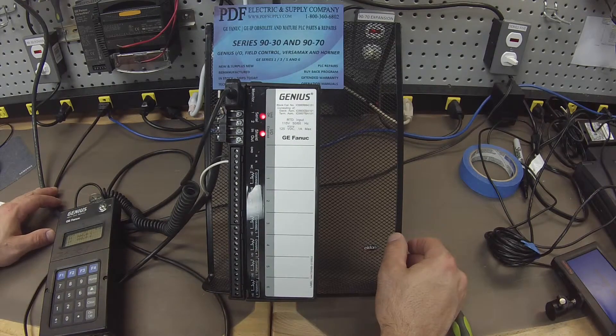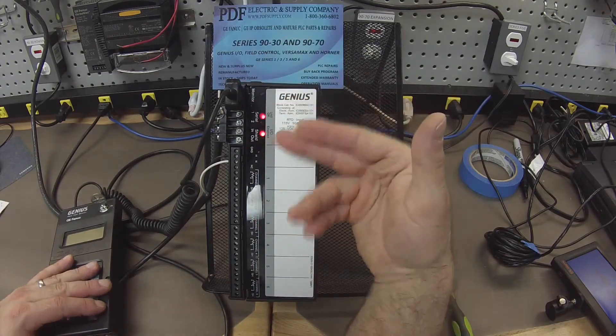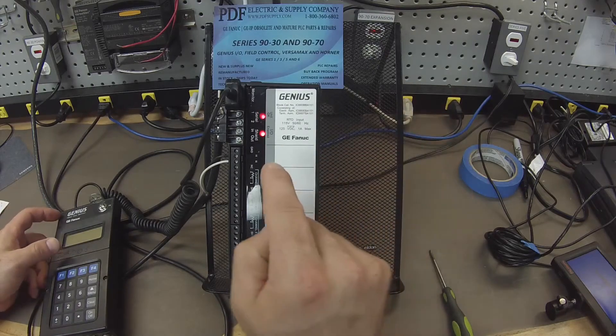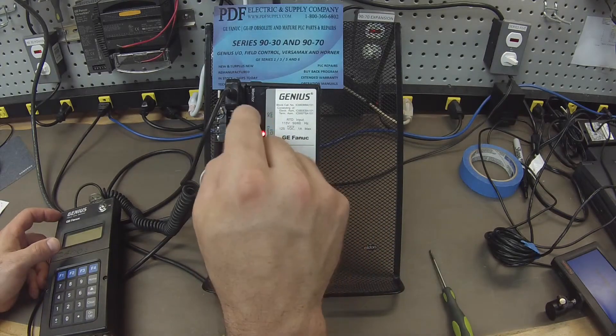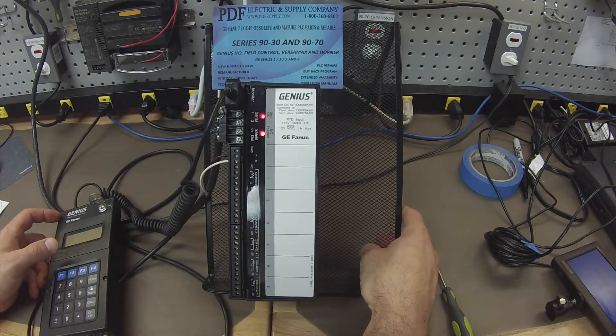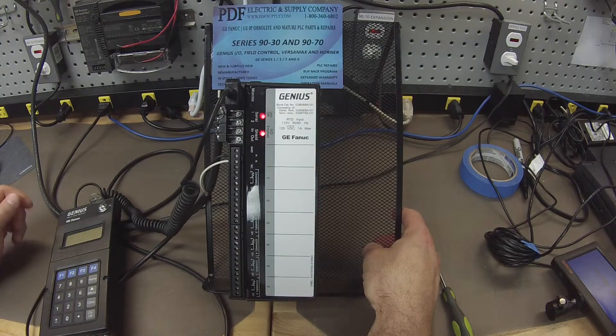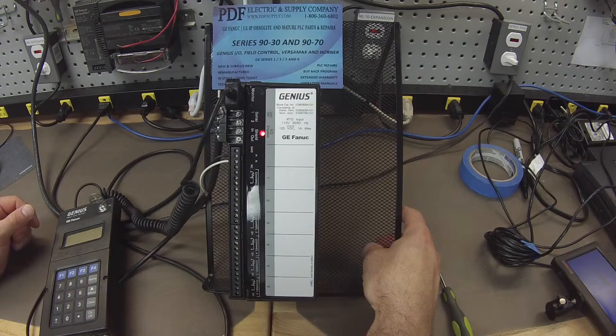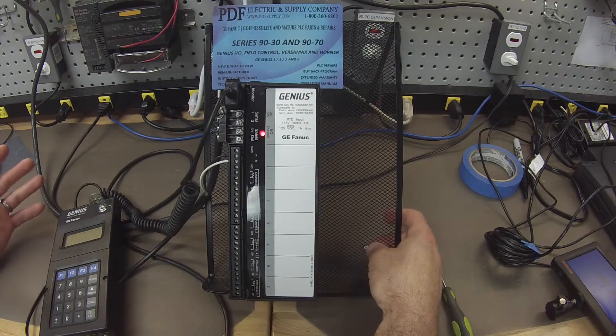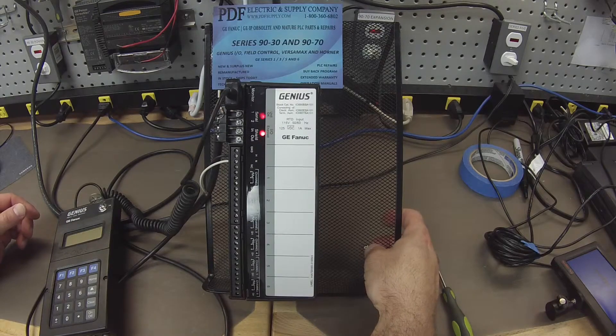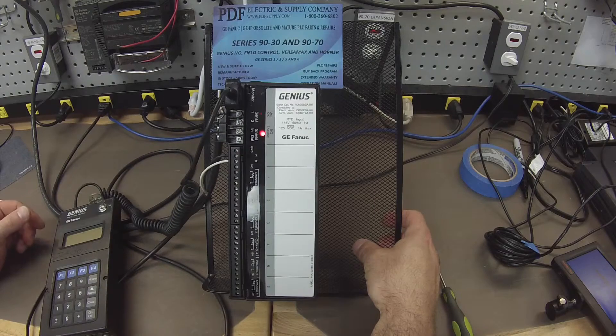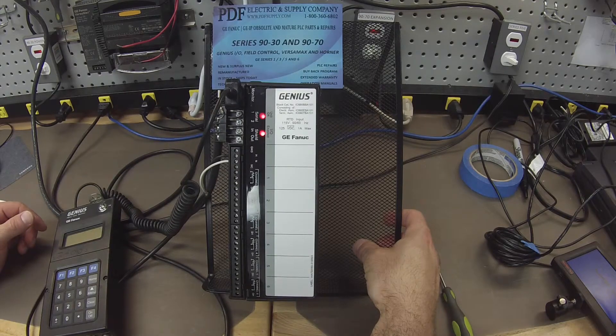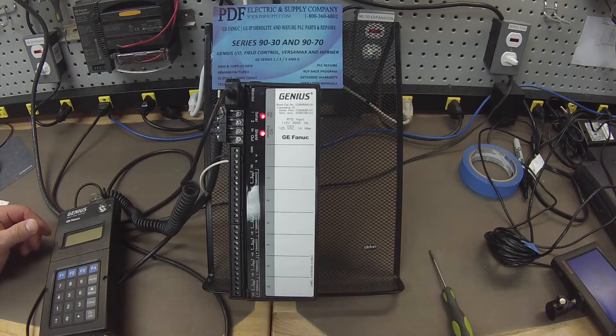Now, if you have any problems with your genius block, if you power it up and you don't have lights that come on, or another thing that we typically see is if you go to the configure ID screen on your handheld monitor, that's the IC660HHM501. And instead of getting a block number, you get a question mark where it is unable to store a configuration. These are common problems that we see with genius blocks, and it's something that we repair. We offer exchange programs, new and remanufactured products with same-day shipping. So if that's something that you need or interests you, please see us at PDFsupply.com. Thank you.